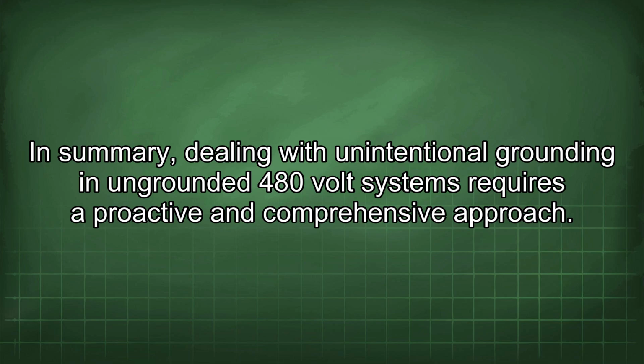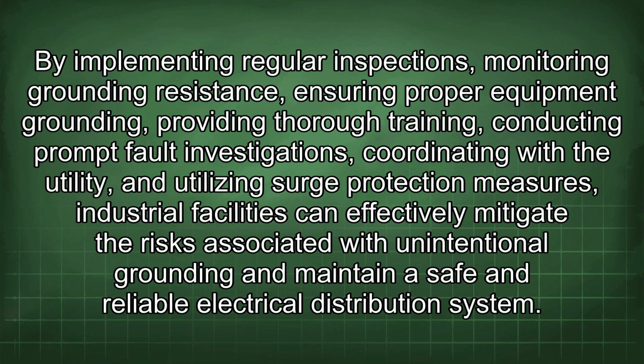In summary, dealing with unintentional grounding in ungrounded 480-volt systems requires a proactive and comprehensive approach. By implementing regular inspections, monitoring grounding resistance, ensuring proper equipment grounding, providing thorough training, conducting prompt fault investigations, coordinating with the utility, and utilizing surge protection measures, industrial facilities can effectively mitigate the risks associated with unintentional grounding and maintain a safe and reliable electrical distribution system.